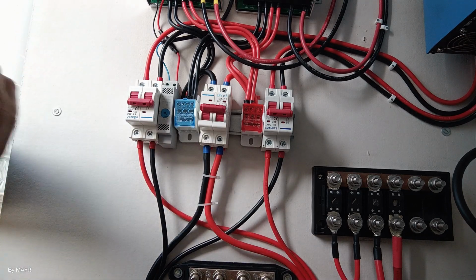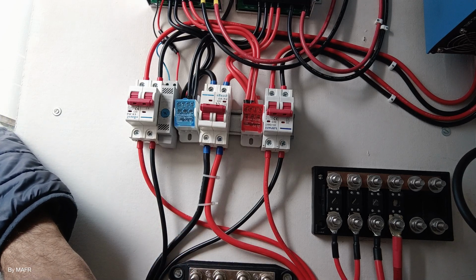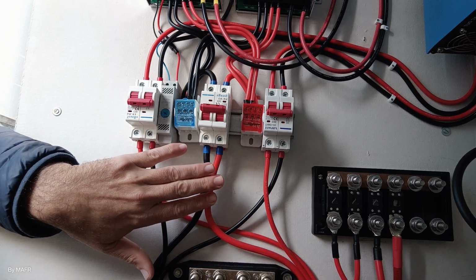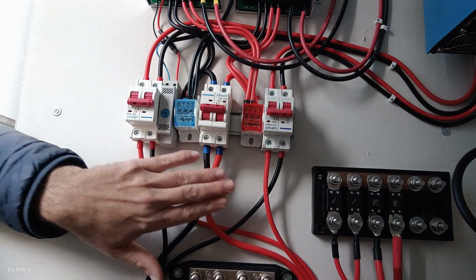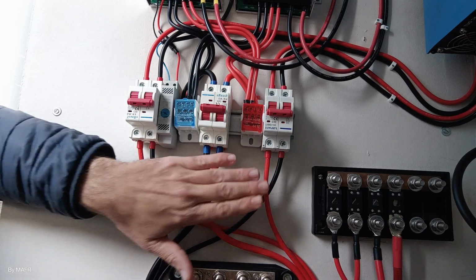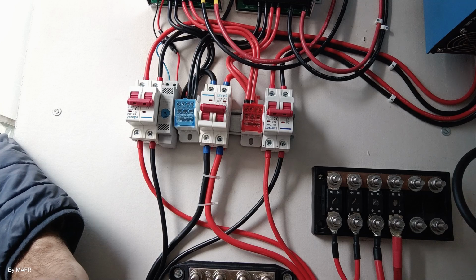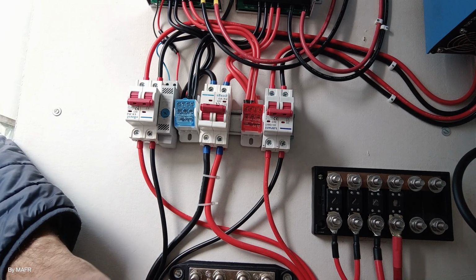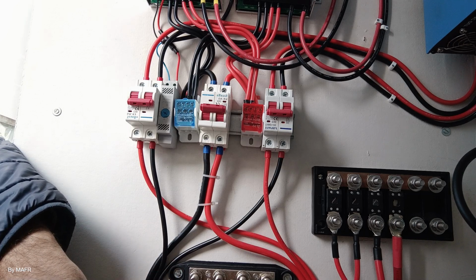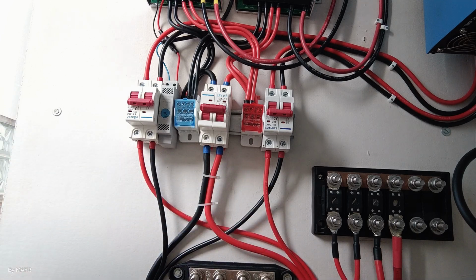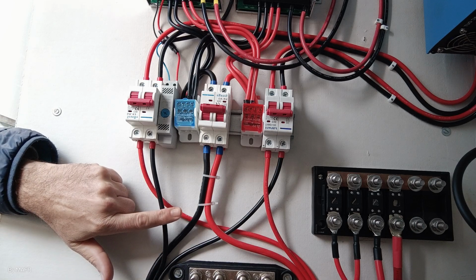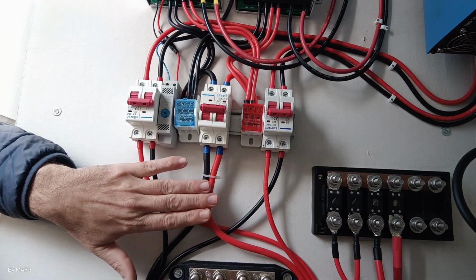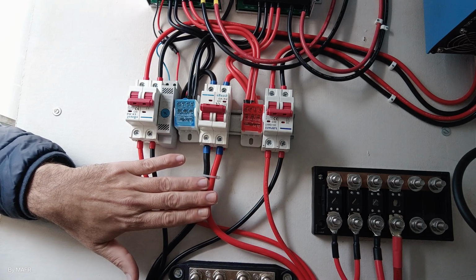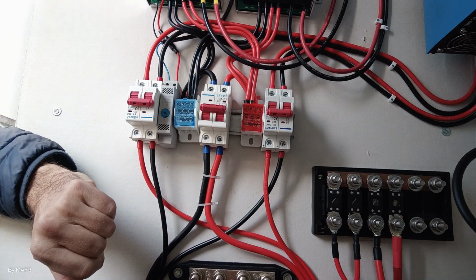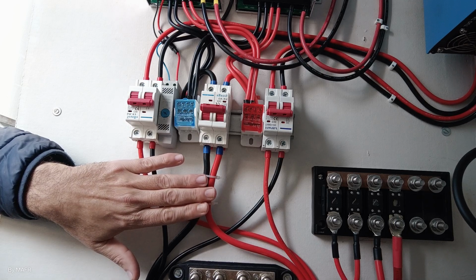So all in all, when working at maximum, I have 50 amperes coming from the charge controllers, and I have 40 amperes pulling to the inverters, right? When I have this working, it's able to generate about 2000 watts. The inverters will actually pull 1800, because they can handle 1000 each, but I have put the limit there to a maximum of 900. And the solar panels that I have can completely feed the inverters, pulling minimum power from the battery, right?